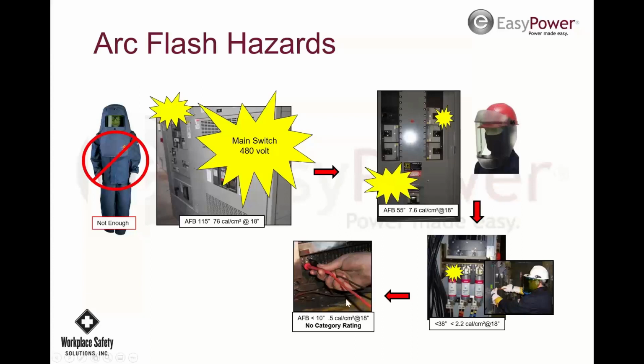Now the thing to remember on this one, this is a depiction of what actually happened to this gentleman. One of his probes went past the screw and made contact with the case, and there was an arc flash event. It's only 0.5 calories per square centimeter, less than 1.2. But you have to remember, this is at 18 inches. So this is the protection level. You don't need any specific protection level at 18 inches if you've got only 0.5 calories. You don't need a shield. You don't need arc-rated clothing. But at his hands, he got second-degree burns because it's at 2 inches, a much higher arc flash level.